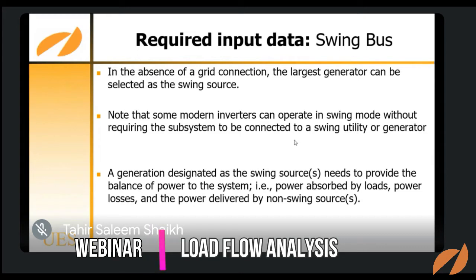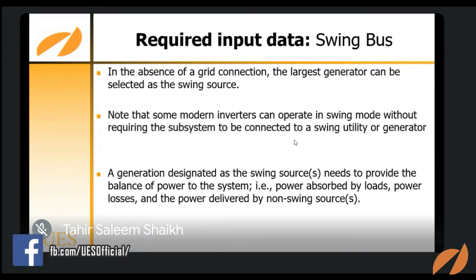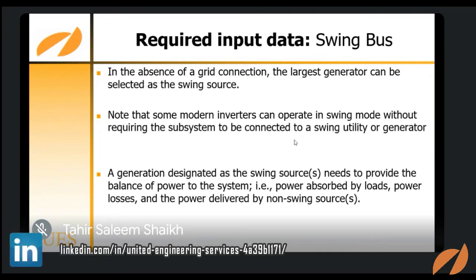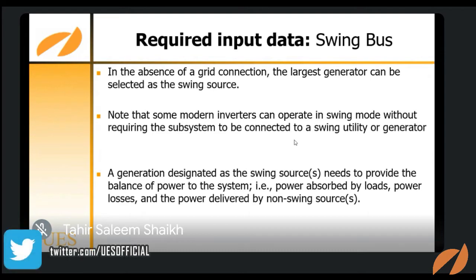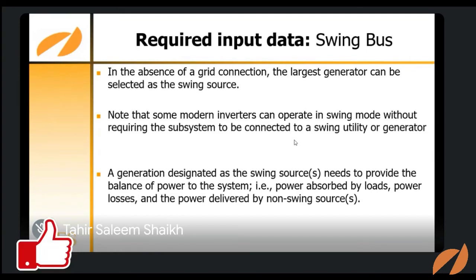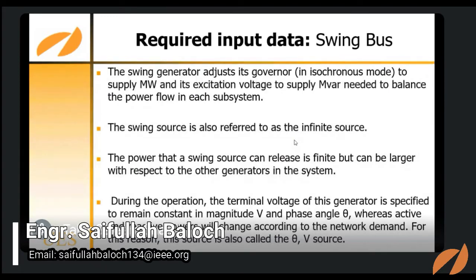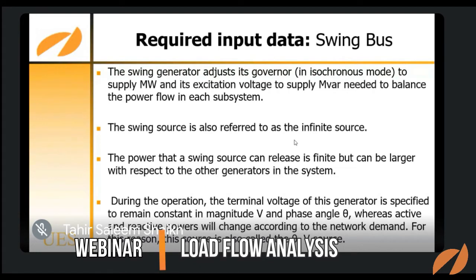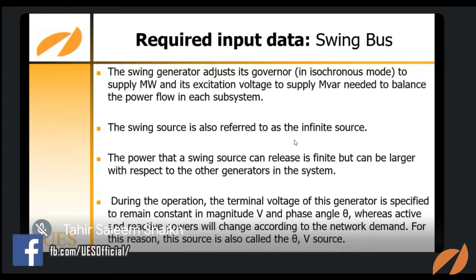Okay, if there are many generators connected with each other, then the largest generator is selected as the swing source. And in the absence of a generator, the grid is referred to as the swing bus, because as we know, WAPDA or any utility company is an infinite power supplier, an infinite power utility. So it is referred to as an infinite bus. So in the absence of a generator, the grid is actually referred to as the swing bus, and it is responsible for the power flow. And the swing bus, as I already told you, is an infinite source. If we consider real-time parameters, it is not actually infinite, it is finite, but it is larger in comparison with the other kinds of sources.